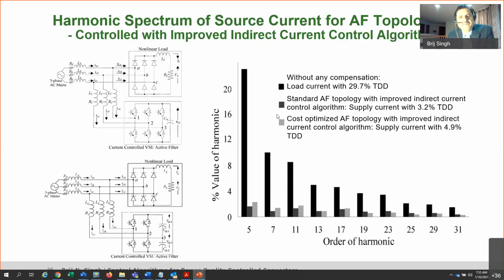But if you could reduce the harmonic by passive filtering to, let's say, 10%, then the rating of this converter can drop from 30 kilowatt to 10 kilowatt. And if you compensate the 11th and 13th so that even the 5th harmonic is down to 6%, then suddenly this converter is rated at only 6 kilowatt. So we're talking about an order of magnitude difference here, 30 kilowatt versus 6 kilowatt rating.